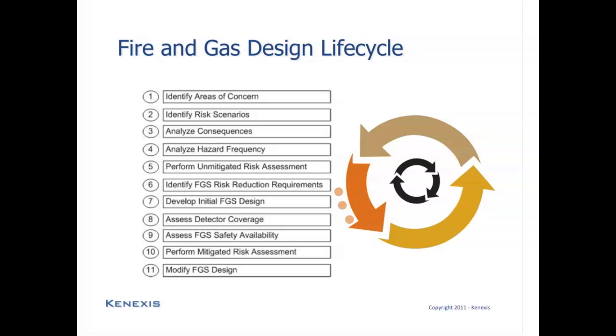After the initial design has been laid out, the detector coverage is calculated. So the effectiveness, in terms of how much coverage a fire and gas detector array can achieve, is specifically calculated instead of simply looking at the rules of thumb and using that as the final arbiter on where equipment should be placed. In addition to the coverage, we'll also calculate the safety availability of the fire and gas equipment. The electrical equipment that is in the control loop will be calculated, the safety availability will be calculated in the same way that a SIL would be calculated for a safety instrumented function in accordance with the IEC 61511 standard.